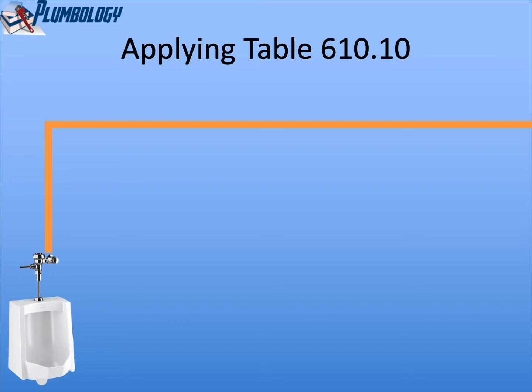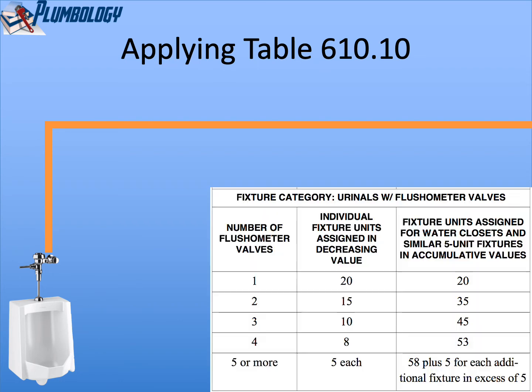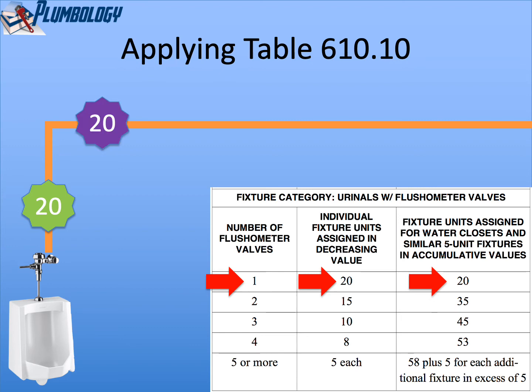Now looking at urinal flush valves. If we have a single urinal with a flushometer valve, according to the table for the category of urinals with flush valves, one urinal flushometer valve will be given a value of 20 fixture units. So we write 20 near the flush valve. The accumulative value would be 20, and the pipe serving that flush valve would be sized for 20 water supply fixture units.